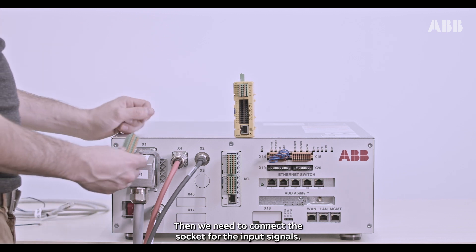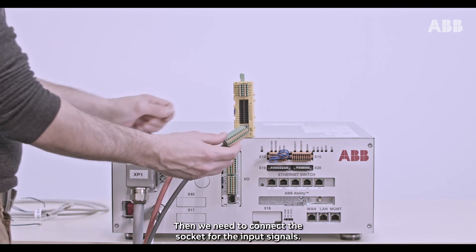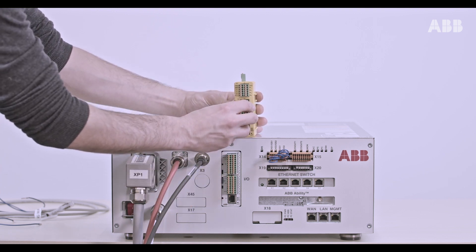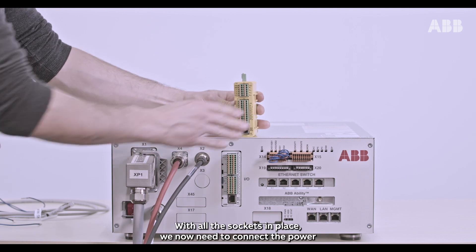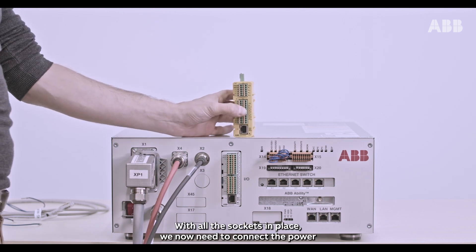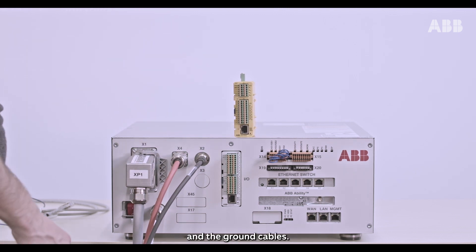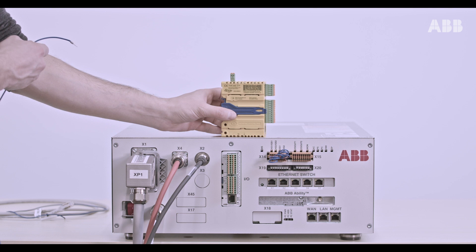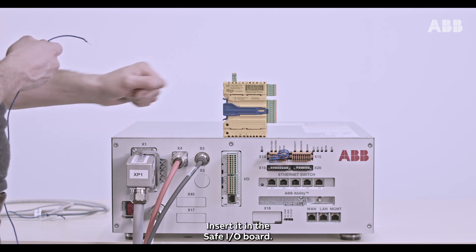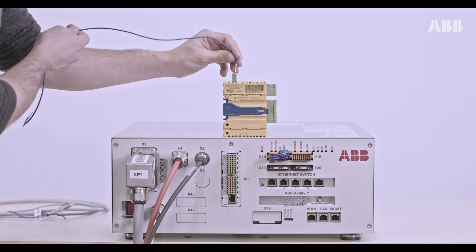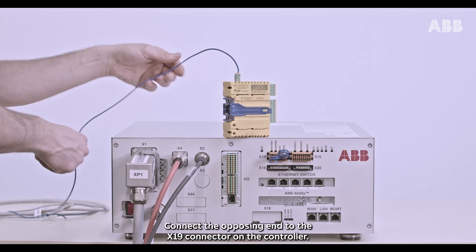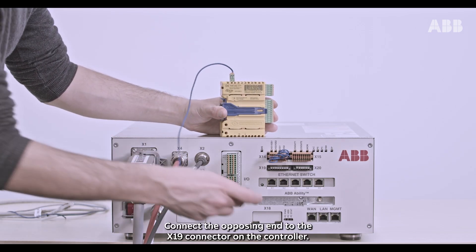Then, we need to connect the socket for the input signals. With all the sockets in place, we now need to connect the power and the ground cables. Let's start with the ground cable. Insert it in the safe I.O. board. Connect the opposing end to the X19 connector on the controller.